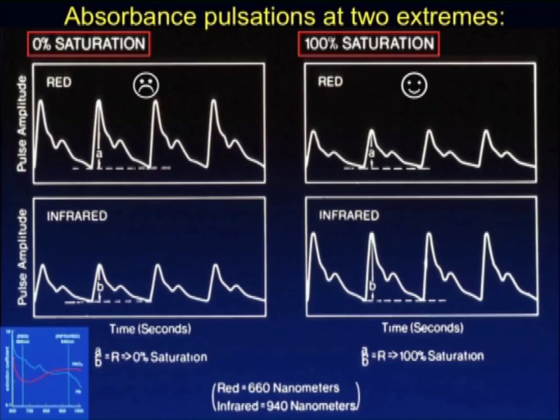Now go to the patient who's very unhappy. He's got 0% saturation, and we look at the reduced hemoglobin curve, and it makes sense. The infrared has the low absorbance, and the red has the high absorbance, and so you get the large pulsations in the red, low in the infrared. And so if you take this ratio called red over infrared, shown here as A over B, it ought to somehow correlate or relate to the ratio of oxyhemoglobin to total hemoglobin or reduced hemoglobin in the arterial blood. And we're going to assume that this is specific to arterial blood because that's Aoyagi's assumption. Everything that pulsates is arterial. Now again, I've done that without equations because that's exactly how Aoyagi did it.